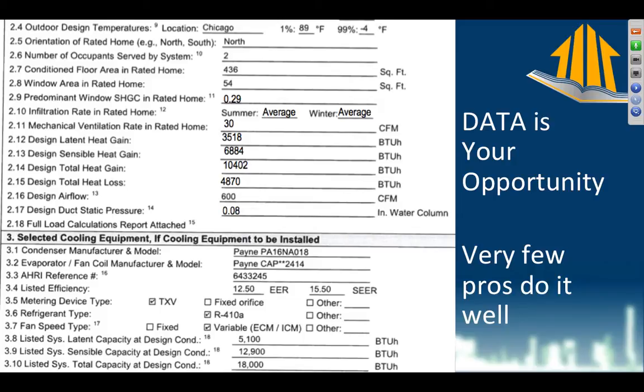The first two things that always happen are: you need to do a heat load calculation, for both heat loss in winter and heat gain in summer, and then select the equipment. Data is the key to all of this. This checklist is made up of numbers, checkboxes, and information about the house or apartment we're designing a system for. Very few professionals actually do this with any degree of competency, and I'll show you why.